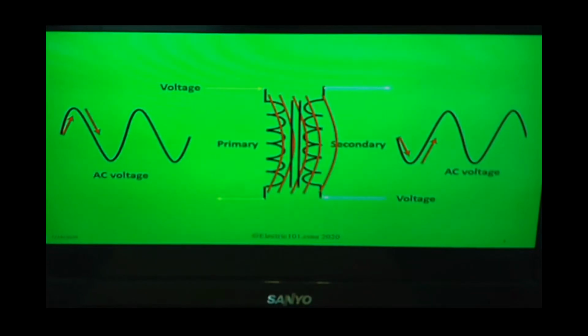Now, as this sine wave right here rises and falls, you see the arrows rise and fall, and that magnetic field expands and contracts. As that power flows through the primary windings, it induces a voltage in the secondary windings in the opposite direction. So that transformer will invert the sine wave. It'll step the voltage up or step the voltage down. That's all based on turns ratios.